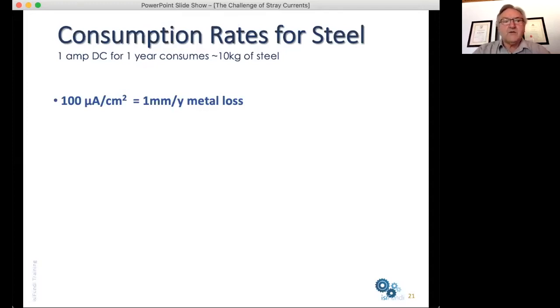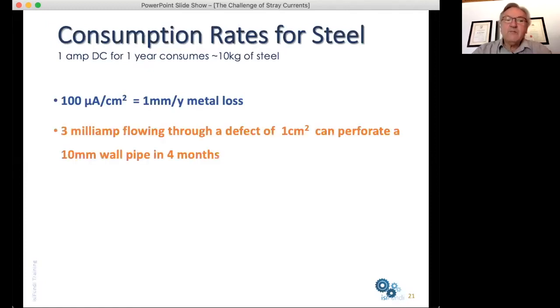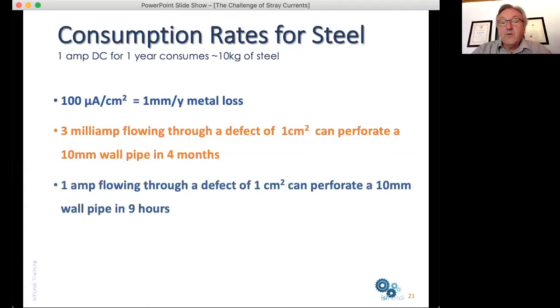Now, how on earth do you imagine what sort of current is 100 microamps? Well, a square centimeter is about the area of your fingernail. 3 milliamps is the current taken by an LED, an ordinary LED. So if you had the current needed to energize an LED flowing through a surface area the size of your fingernail, and that represents, for example, a defect on a pipe, the defect being in the coating system, then that current can perforate a 10 millimeter wall pipe in 4 months. That's scary. If we push it up to 1 amp, we can perforate a pipe in a matter of hours. So you can see that compensating for these stray currents is a really serious situation.